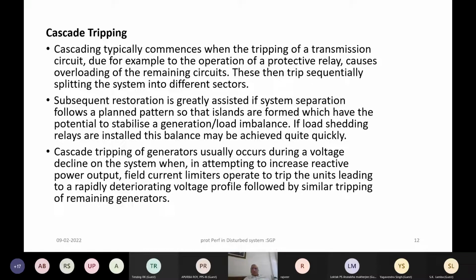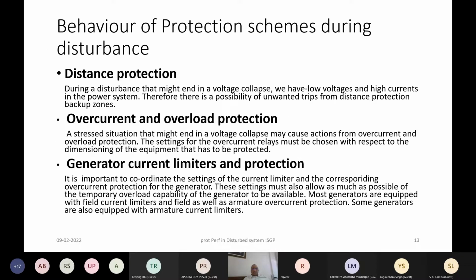So for long 400 kV lines, we need to ensure that during the dynamic condition when such an overload occurs, the lines do not trip due to distance protection. Because if one line trips, the loading will get diverted to the parallel line. The parallel line will also then trip, and this cascading effect will continue on other corridors which are in parallel. So this is an important aspect as far as grid collapse prevention is concerned, how to prevent cascade tripping. Which are the protections which play a role? Primarily distance protection.